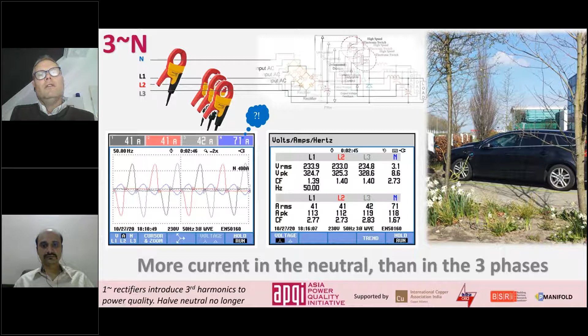Does the fuse blow? Mostly not, because most systems have fuses in the phases and not in the neutral. So when you look at the harmonic picture, I have put some arrows at the place of the third harmonic. The multiples of the third harmonic, you can add them on top of each other, because the third harmonic, the 9th harmonic and the 15th harmonic are at the same time pointing in the same direction, and that is why the amps in the neutral add up. So we have 41 amps going into the chargers, and then 70 amps going out. That's terrible.